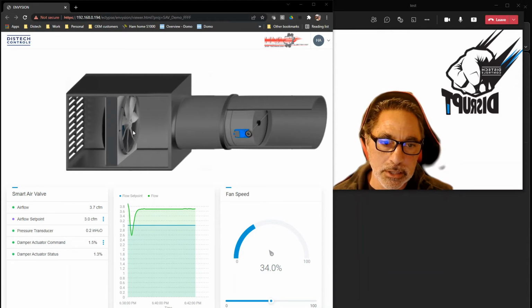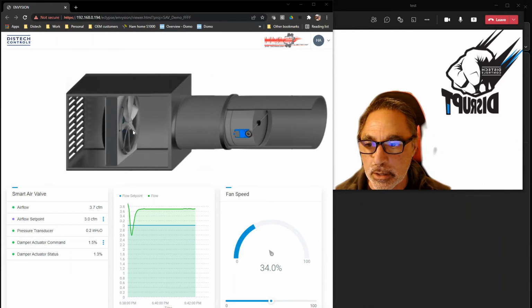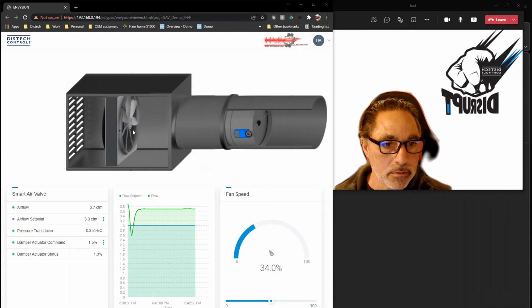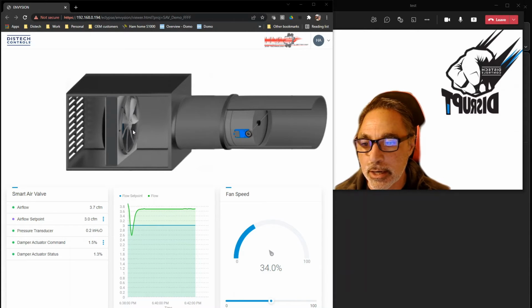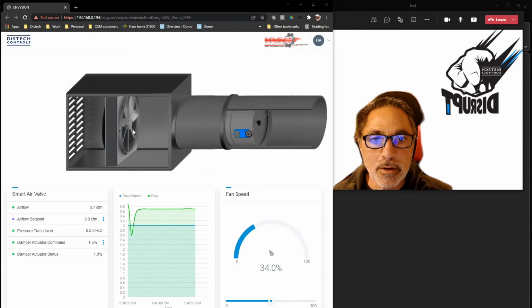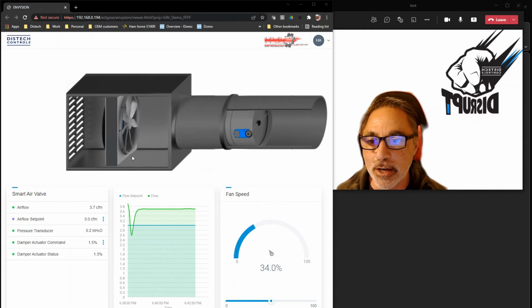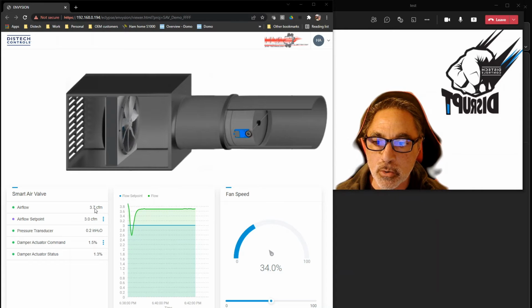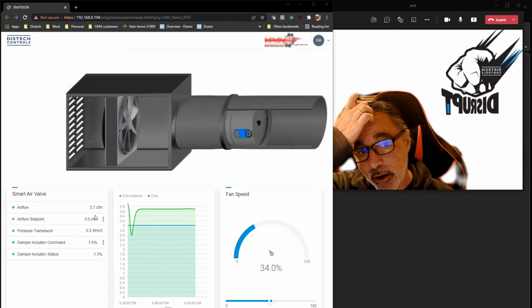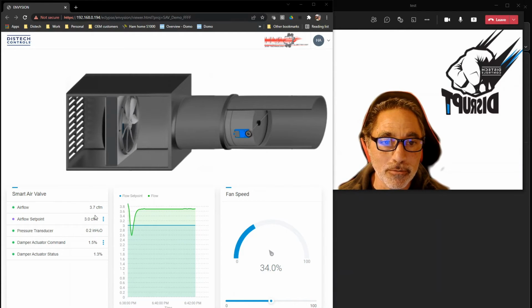So I obviously needed some sort of a fan for it to push some air through so I could show everyone the airflow, the set point, what my pressure reading is, and what my actuator command is doing. As you can see right now, I am running this device at a set point of 3, and I'm actually at 3.7. So I'm only 0.7 CFM off from the actual set point.